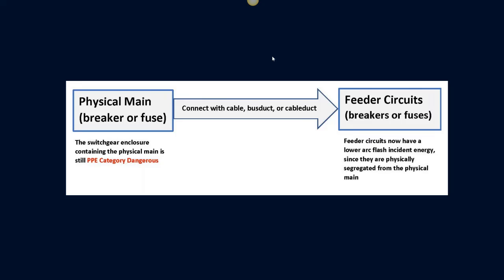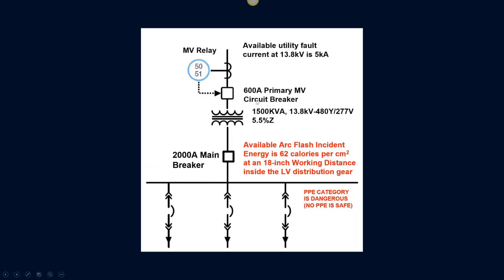But more than that, with the requirements of NFPA 70E and lockout tagout, physical mains, if they're close coupled to the feeder, aren't even a legitimate lockout tagout point, because if you're close coupled, you open the main, you lock it out, the line side of that main is still hot, it still has a very high arc flash incident energy, and therefore so does the rest of the lineup. So if you go to the next graphic, Michael.